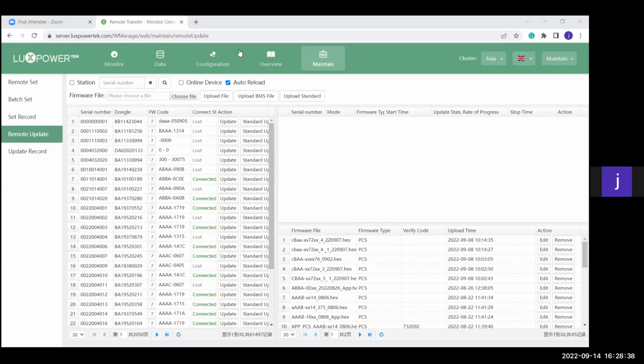Yes, it's safe to do an update on the machines if they are running in parallel mode. I always try to tell the clients, if they are in parallel mode, to switch off the output breakers of the inverter so that the 2 inverters are not connected to each other, because it will give a parallel fault as soon as one inverter goes to the new firmware and the other one is slightly behind. So that's usually how it is done. I'll explain exactly what the recommendations are on a parallel system, so that you can see what I mean by switching off the outputs of the inverter on the circuit breaker side.